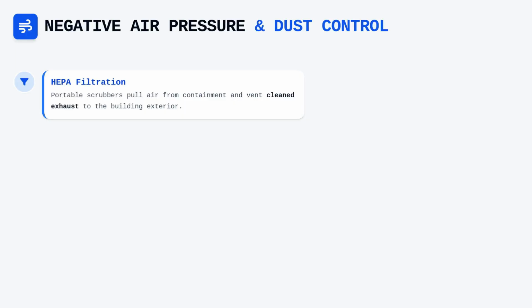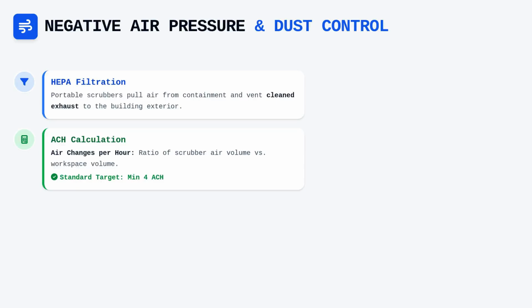To ensure this system functions as intended, you must calculate the air changes per hour, ACH, which is the ratio of the volume of air handled by your scrubber relative to the volume of the workspace. A standard requirement for effective dust control often targets a minimum of 4 air changes per hour, though high-risk environments may demand considerably higher volumes.